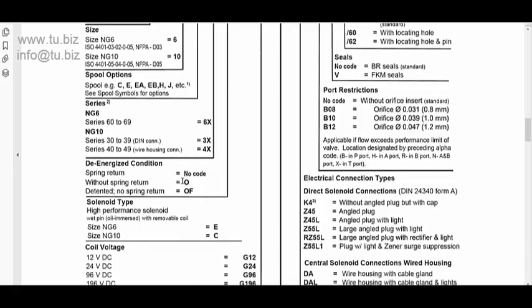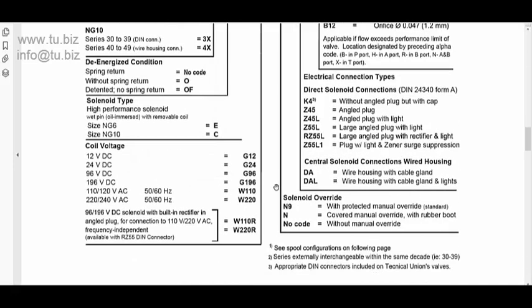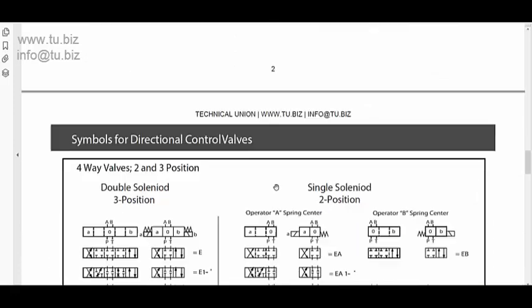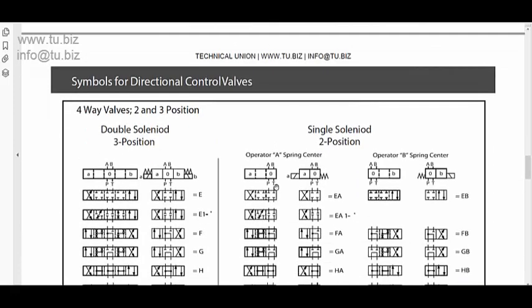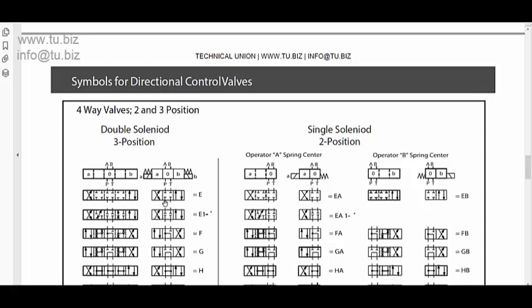Then on the de-energize, either if you want a detent or a spring return, the spring return will automatically put the valve back in the normal position. Like over here, for example, this is the normal position with a closed center. You energize it, it'll go one direction, or you energize it, it'll go in the other direction. But then when you de-energize it, the spring return will automatically return the valve to normal position.